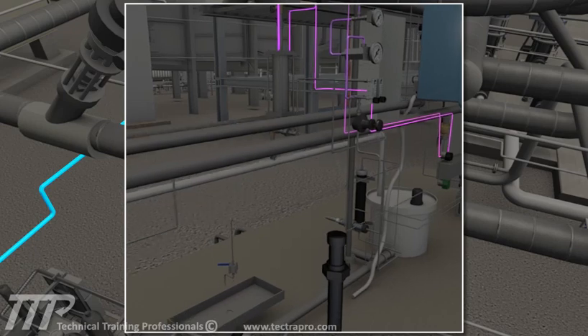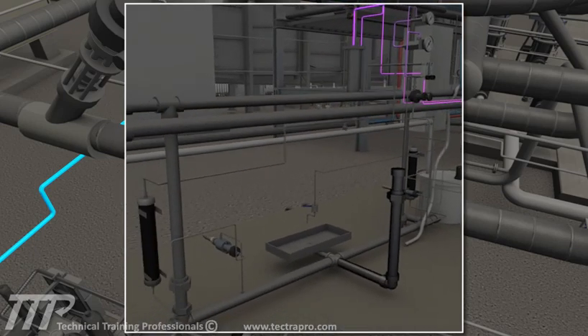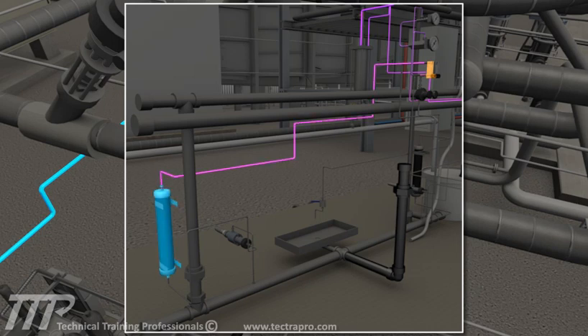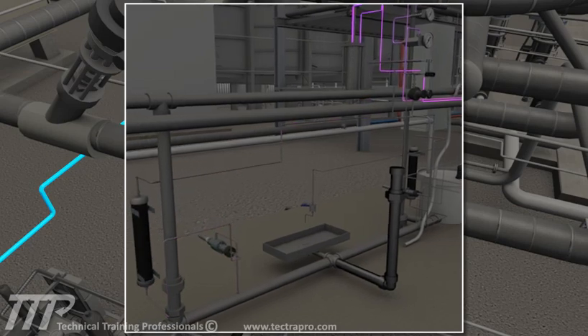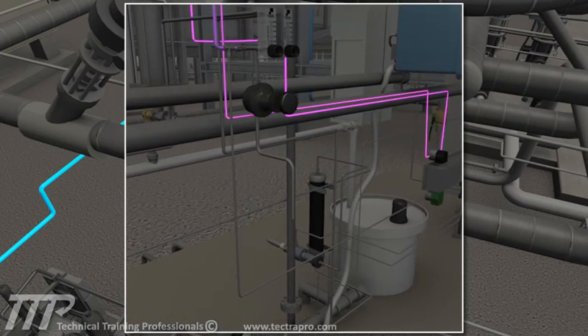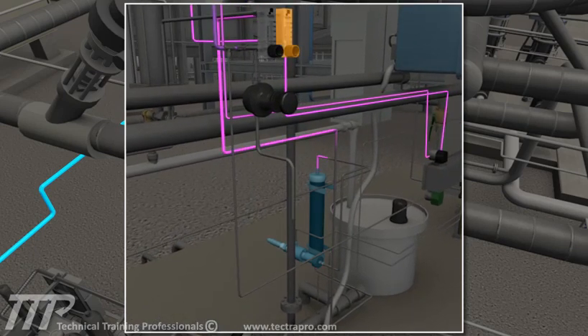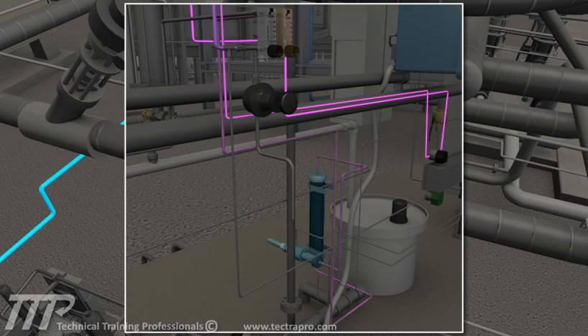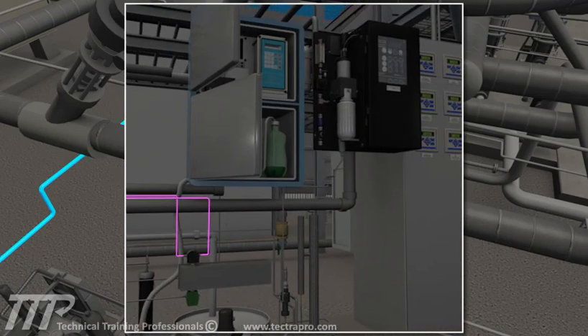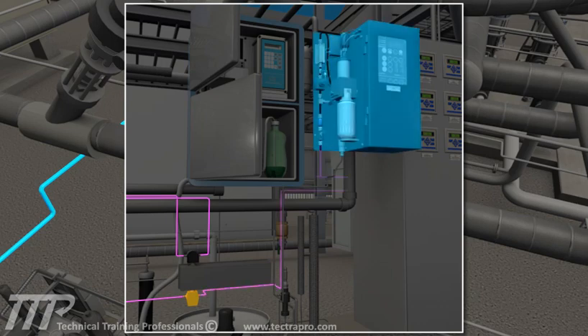From here, the sample is divided into three streams. Stream 1 flows through a flow control valve, resin column, and a cation conductivity analyzer. Stream 2 flows through a flow control valve and degassed cation conductivity analyzer. Stream 3 flows to a sequencer-controlled solenoid valve, which directs it to the sodium analyzer as required.